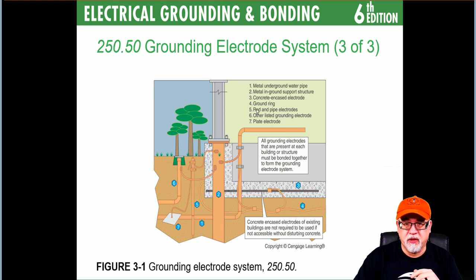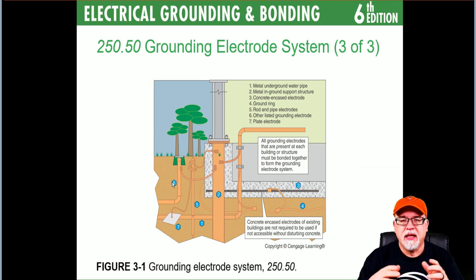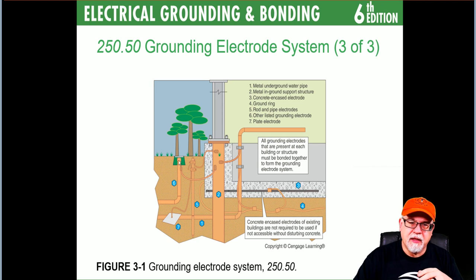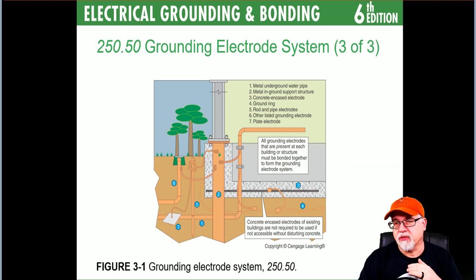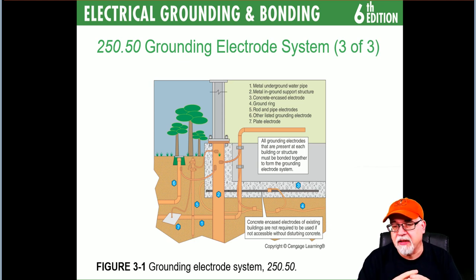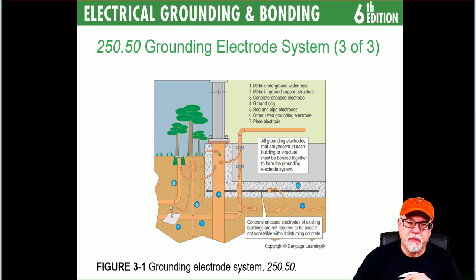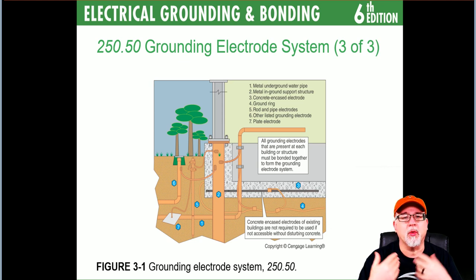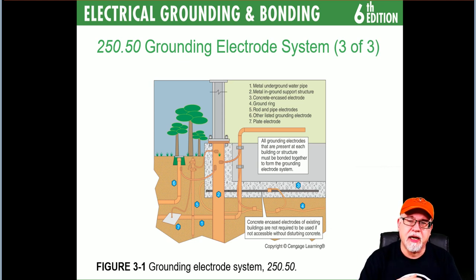Number six is other listed grounding electrodes. One example is a chemical rod where you put certain chemicals in it and it saturates out into the earth — it has a connection made to it. If it's listed for grounding as a grounding electrode, you can utilize it. And number seven is the plate, which gets placed into the earth. There's a required amount of surface area, which we'll cover in the program.